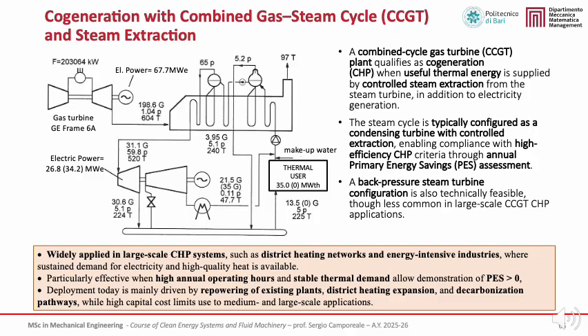An important aspect of this CCGT configuration is that even in the absence of a thermal load, for instance for district heating during summer season, the plant maintains a very high electrical efficiency. This is because the exhaust heat from the gas turbine is already recovered in the steam cycle and converted into additional electrical power, rather than being rejected to the environment. As a result, when no steam is extracted for cogeneration, there is no significant quantity of heat that could otherwise be converted into useful energy.